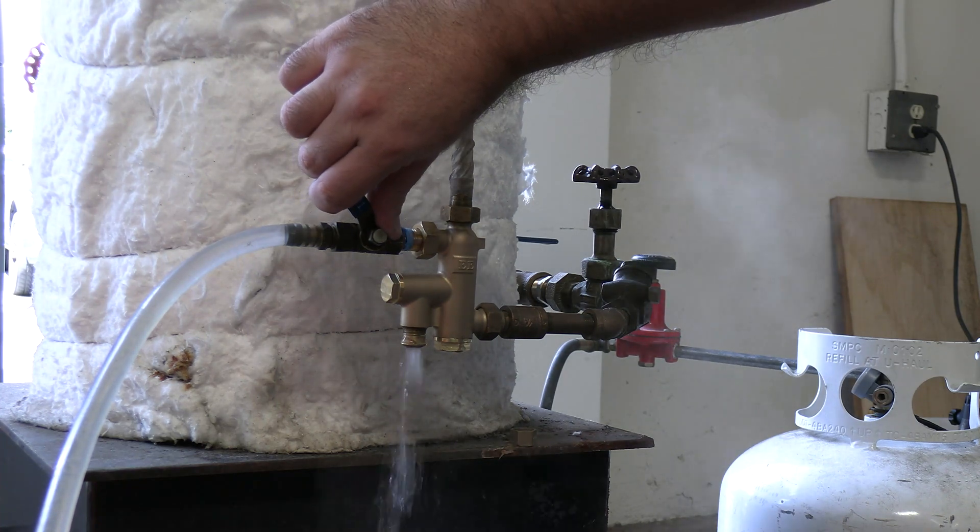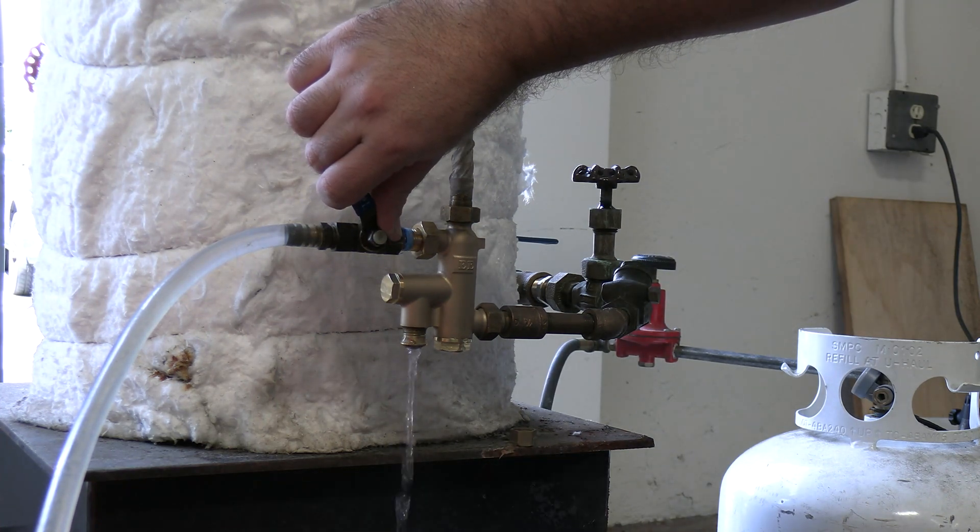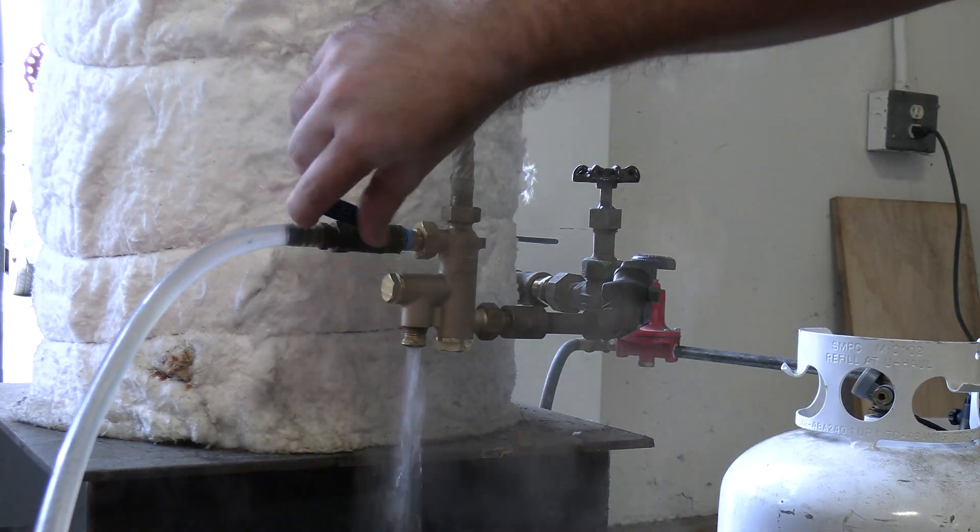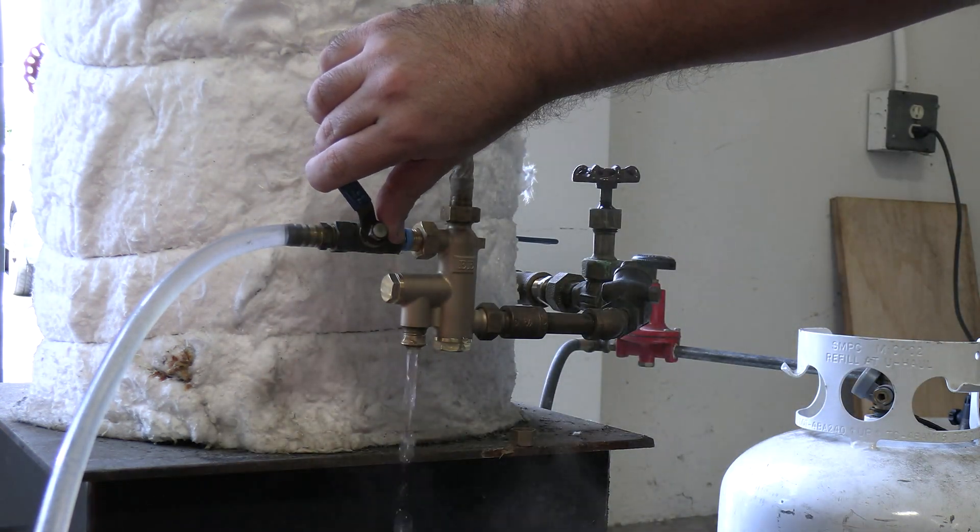When the water valve is restricted further, the steam, air, and water that sputter are doing so in a pulse. This pulsation is very indicative of an air leak.